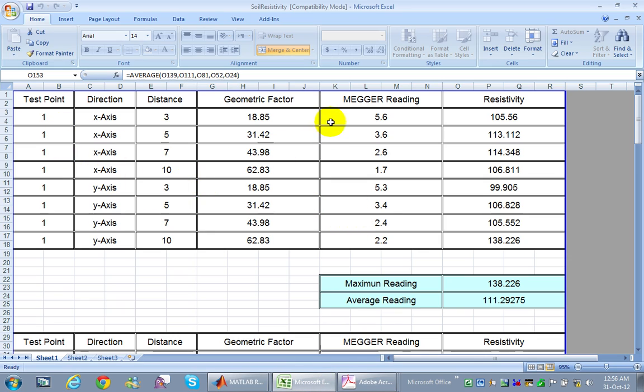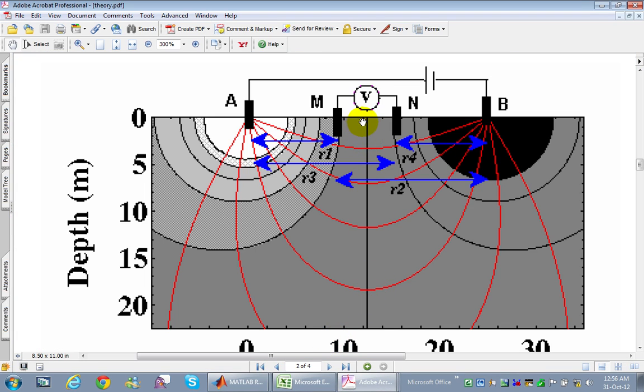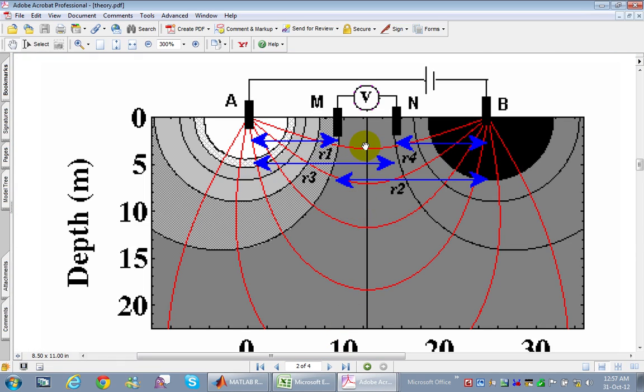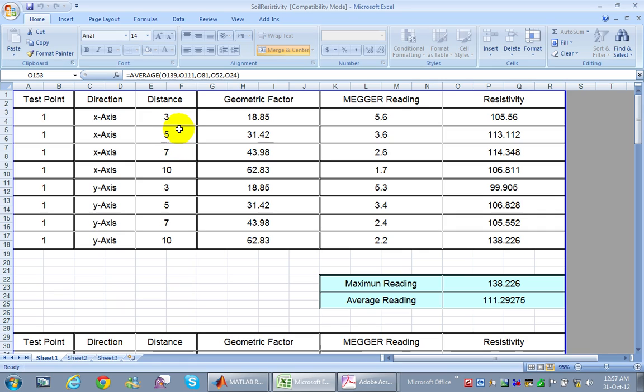Here is a table showing how soil resistivity measurements are made using the Wenner device. We take measurements in many directions and at various distances. In the X direction, with a spacing of 3 meters, the distance between any adjacent electrode pair is 3 meters. We then increase the distance from 3 to 5, 7, and 10 meters.